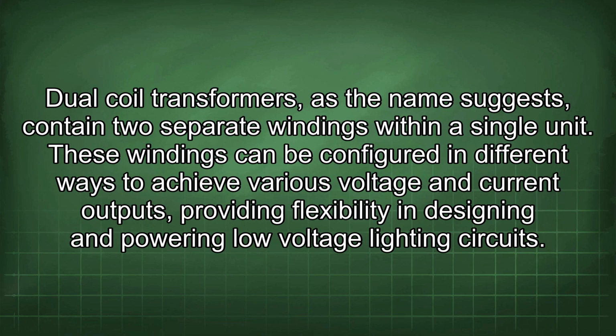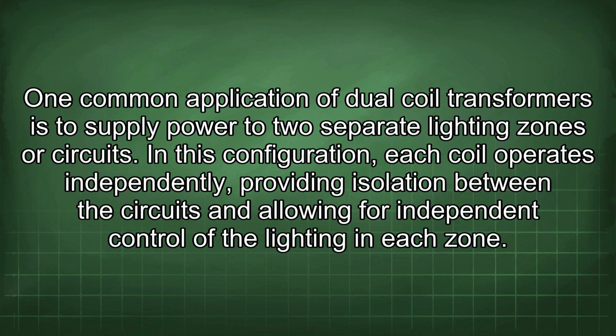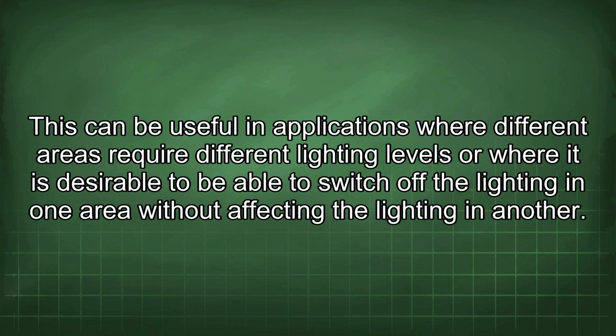Dual coil transformers, as the name suggests, contain two separate windings within a single unit. These windings can be configured in different ways to achieve various voltage and current outputs, providing flexibility in designing and powering low-voltage lighting circuits. One common application of dual-coil transformers is to supply power to two separate lighting zones or circuits. In this configuration, each coil operates independently, providing isolation between the circuits and allowing for independent control of the lighting in each zone. This can be useful in applications where different areas require different lighting levels or where it is desirable to be able to switch off the lighting in one area without affecting the lighting in another.